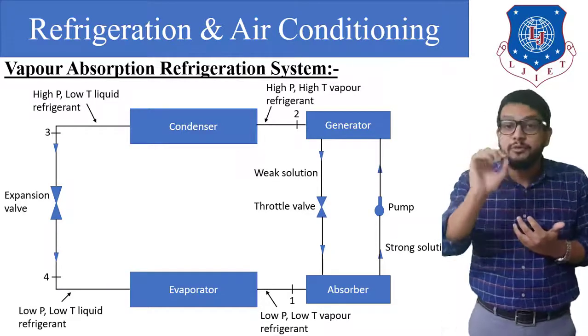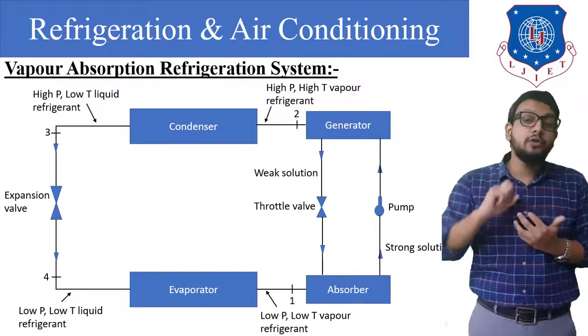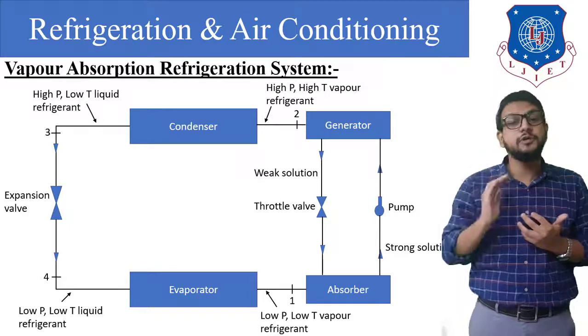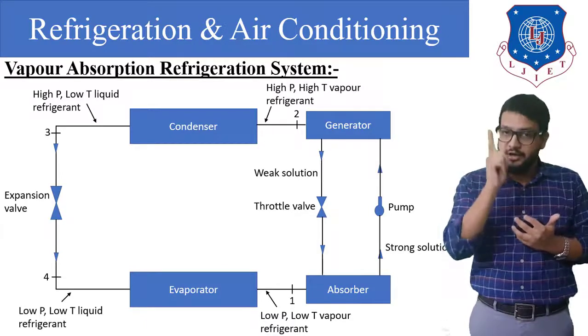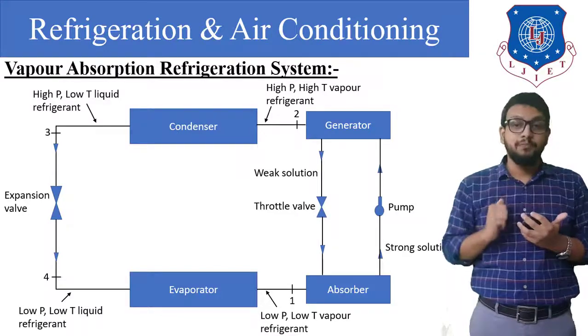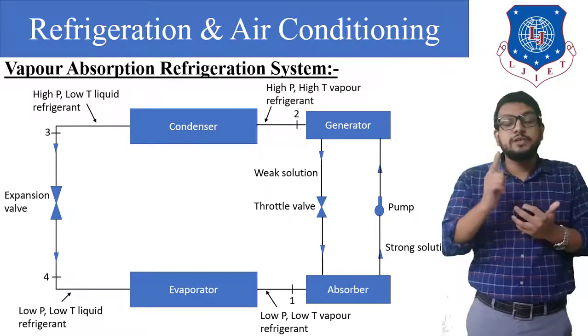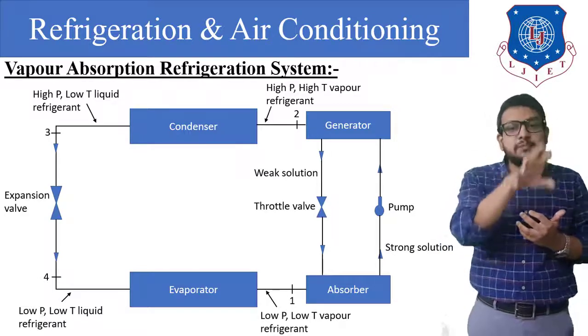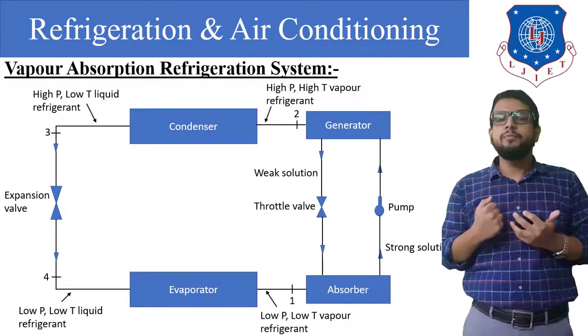At the exit of the generator — point number two — almost 88% vapor ammonia has been released at high pressure and high temperature. It enters the condenser, where heat energy is rejected to the surrounding atmosphere and the ammonia is converted into high pressure, low temperature liquid refrigerant. Remember: in the condenser, temperature is reduced by heat transfer and latent heat is rejected, but pressure remains constant. From point three it enters the expansion device, which reduces the pressure so the evaporator can absorb heat effectively, giving us point four — low pressure, low temperature liquid refrigerant.